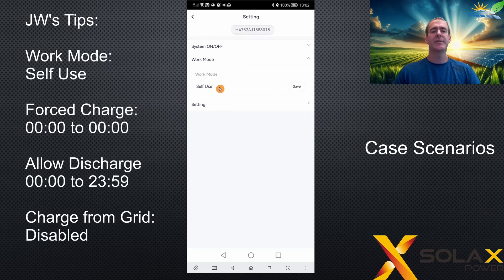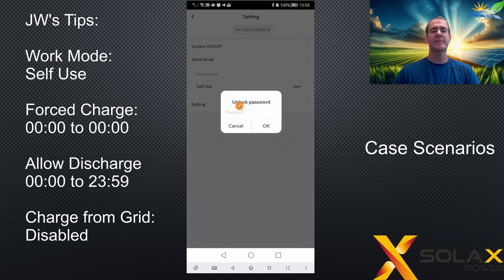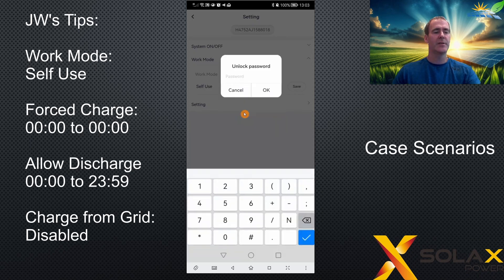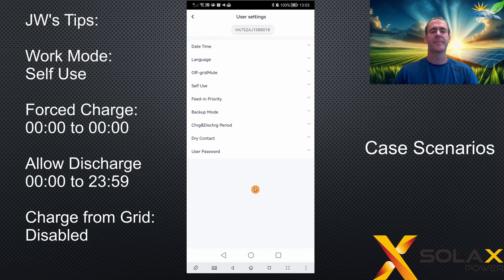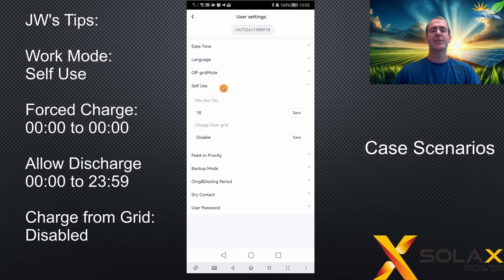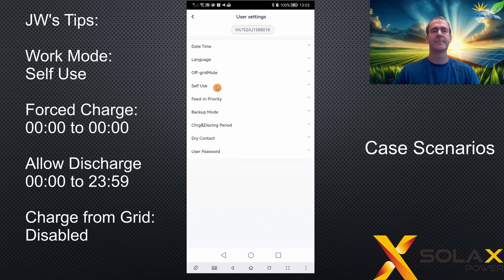First, make sure your work mode is set to self-use. Once you set the work mode to self-use, proceed into the settings and type in the zero-zero-zero-zero code to get into the basic user settings. From there, go into the self-use menu and make sure that charge from grid is disabled, because we don't need to charge from grid in this instance.